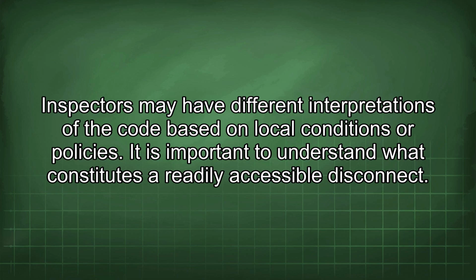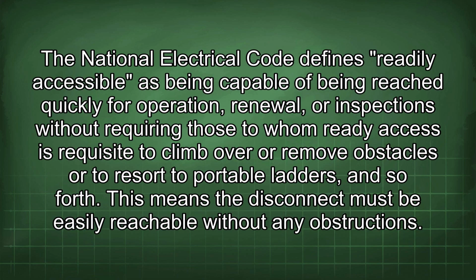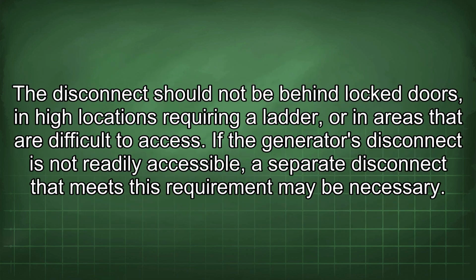It is important to understand what constitutes a readily accessible disconnect. The National Electrical Code defines readily accessible as being capable of being reached quickly for operation, renewal, or inspections without requiring those to whom ready access is requisite to climb over or remove obstacles or to resort to portable ladders, and so forth. This means the disconnect must be easily reachable without any obstructions. The disconnect should not be behind locked doors, in high locations requiring a ladder, or in areas that are difficult to access. If the generator's disconnect is not readily accessible, a separate disconnect that meets this requirement may be necessary.